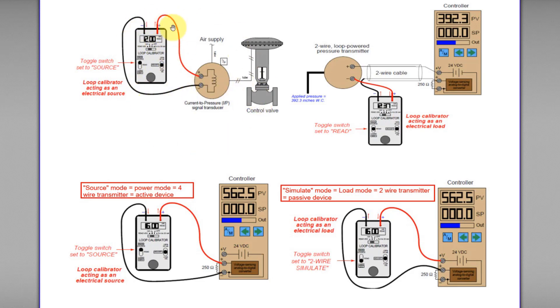This loop calibrator switch is set to source mode. Since it is in source mode, it will act as an electrical source to provide the power to power up the whole loop circuit. Since this one acts as an electrical source, this IP transducer — or current-to-pressure signal transducer — will act as an electrical load. So this loop calibrator not only powers up the whole loop but also at the same time injects a signal.